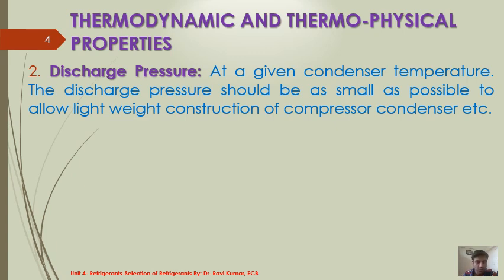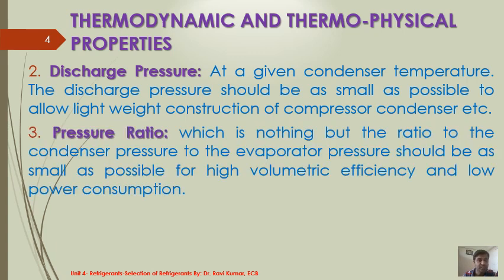Also, the pressure ratio will be small when the condenser pressure is small. So the third point is pressure ratio, which is interlinked with the discharge pressure. This is the ratio of condenser pressure to evaporator pressure, which should be as small as possible for high volumetric efficiency and low power consumption.